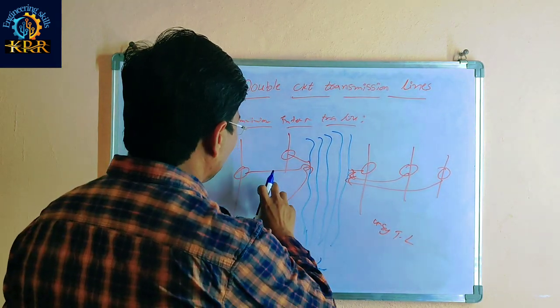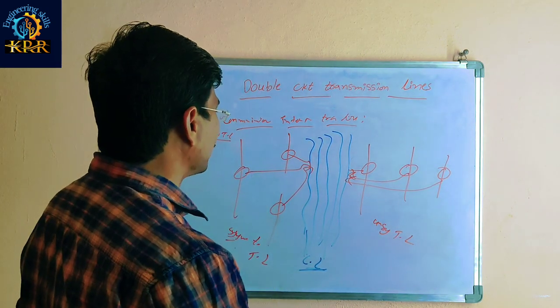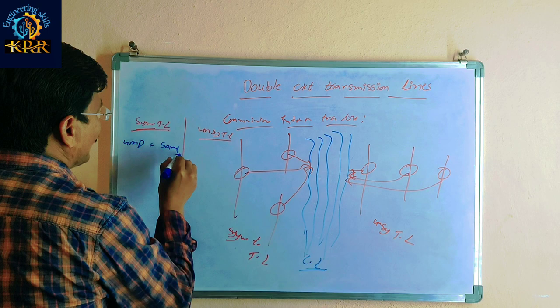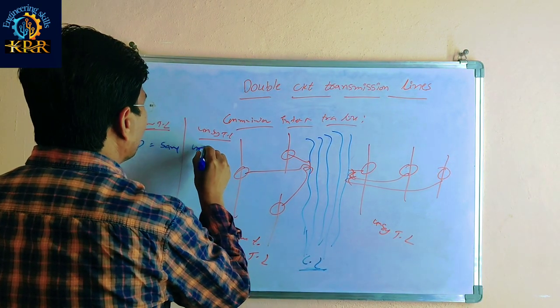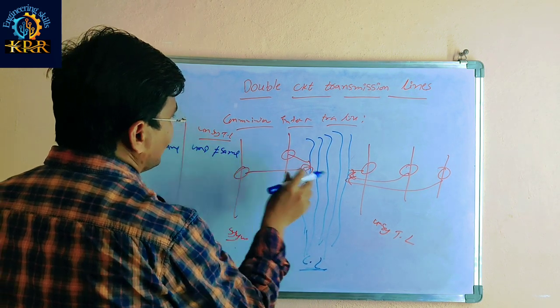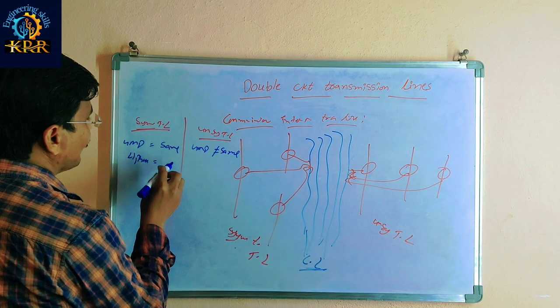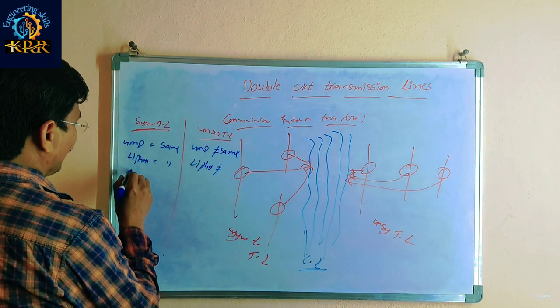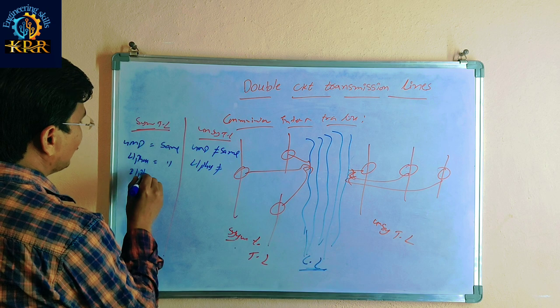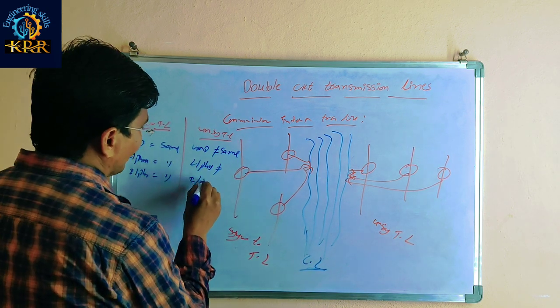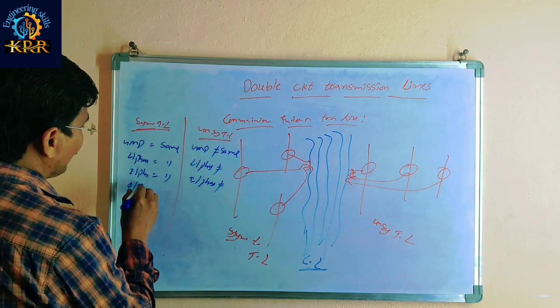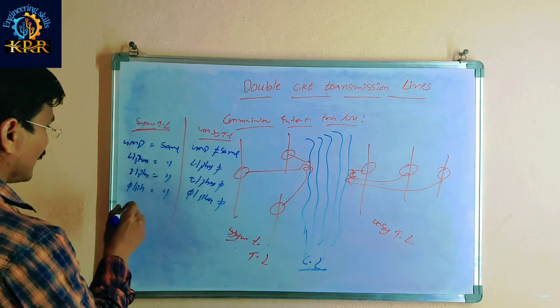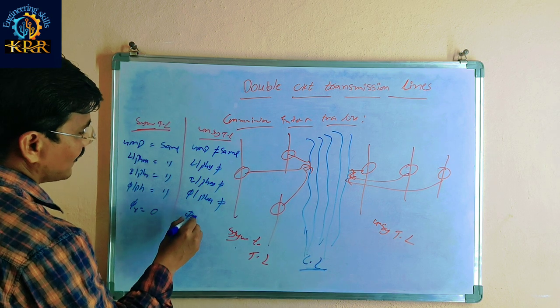In the symmetrical transmission line, the GMD is same. But in the unsymmetrical transmission line, the GMD is not same. Inductance for each phase is same in symmetrical, but here inductance for phase is not same. Current for phase is same in symmetrical, but here current for phase is not same. Flux for phase is same in symmetrical, but here flux for phase is not same. Resultant flux is zero here in symmetrical, but resultant flux is not zero in unsymmetrical.